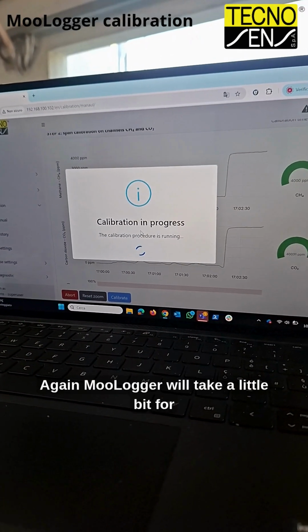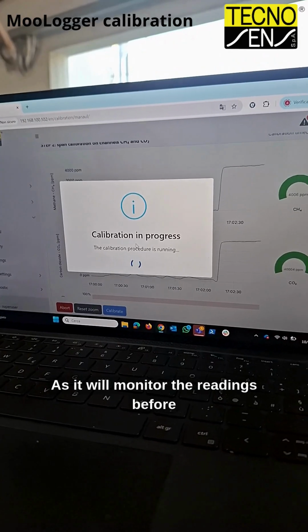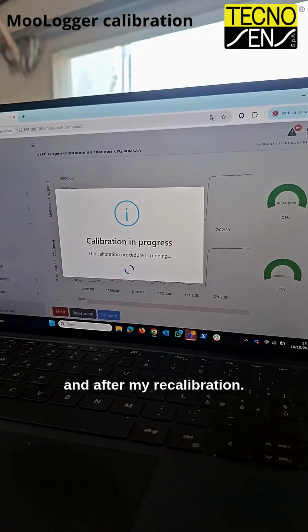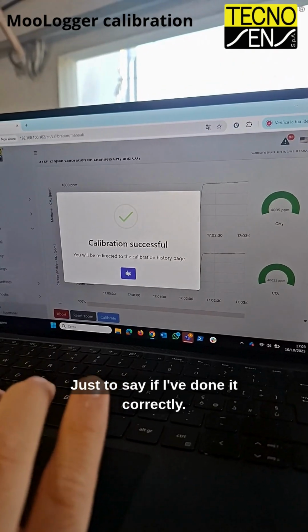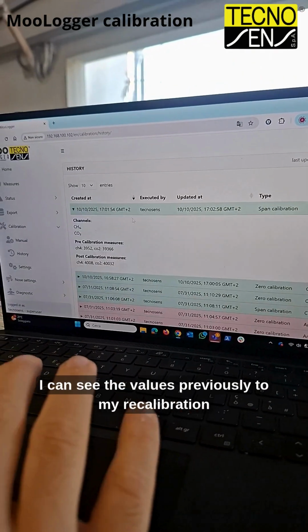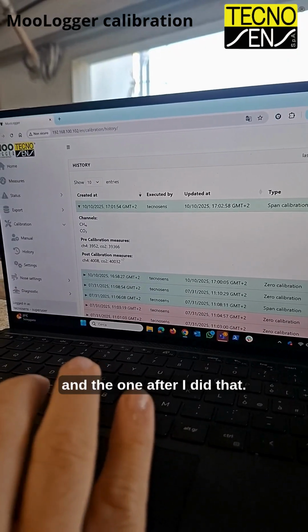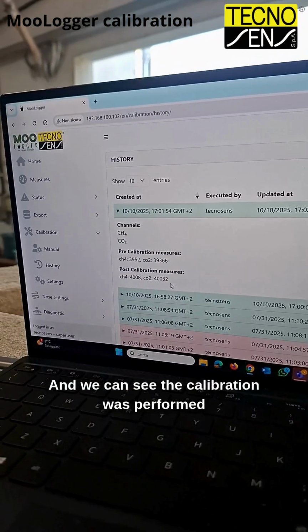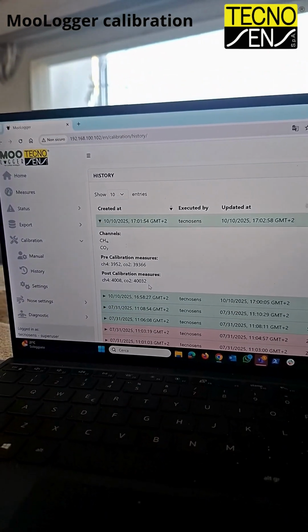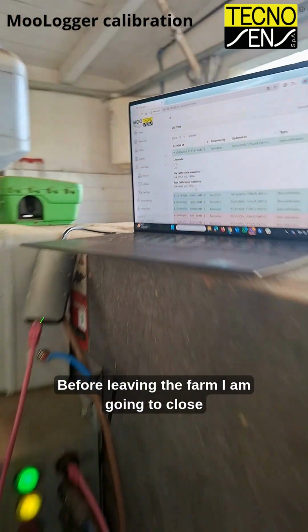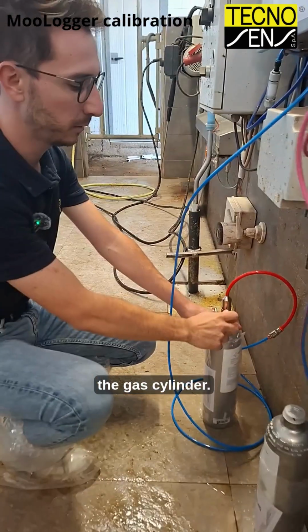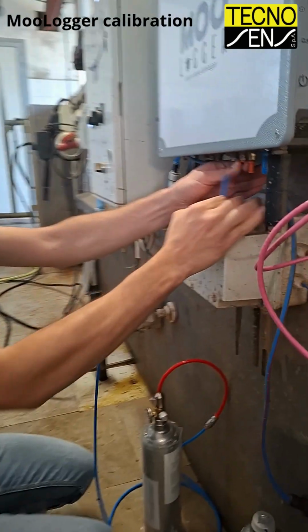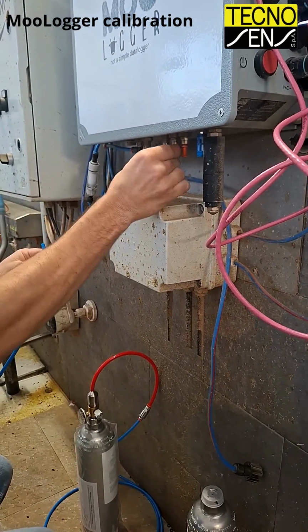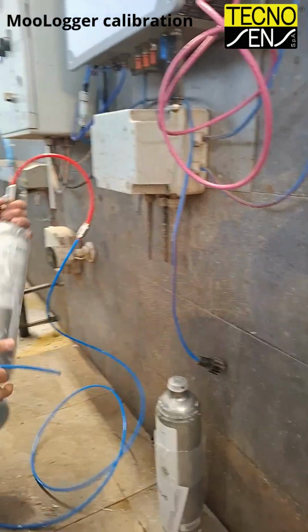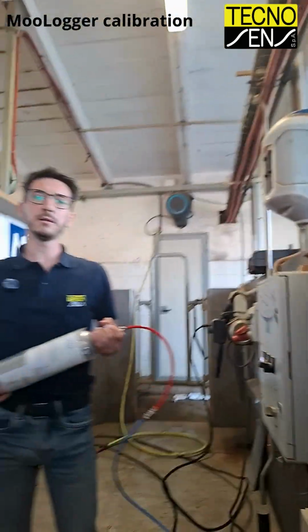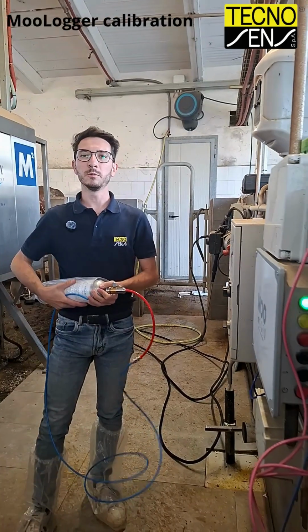Again, the MooLogger will take a little bit for completing the procedure, as it will monitor the readings before and after my recalibration, just to say if I've done it correctly. I can see the values previous to my recalibration and the ones after I did that, and we can see the calibration was performed correctly. Before leaving the farm, I'm gonna close the gas cylinder, remove the tube from the MooLogger input and close it. The recalibration procedure has been performed correctly, and we can now move to another MooLogger or to another location.